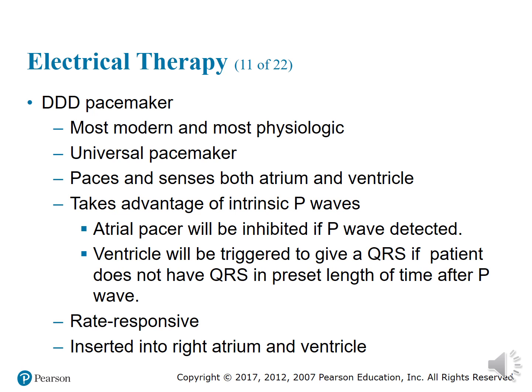The next permanent pacemaker we'll talk about is the DDD pacemaker. The DDD pacemaker is the most modern and the most physiologic pacemaker that they have. It is known as the universal pacemaker and is now the most commonly inserted pacemaker. It paces and senses both atrium and ventricle. A DDD pacemaker is used with AV block.